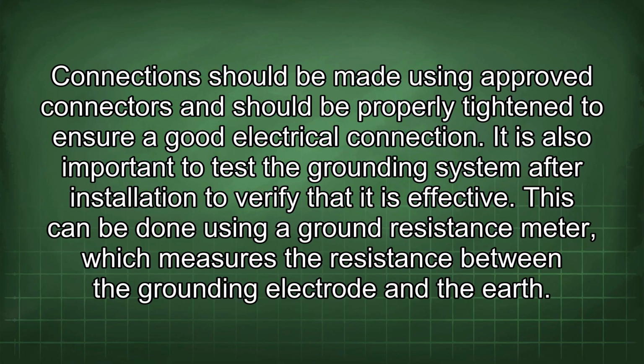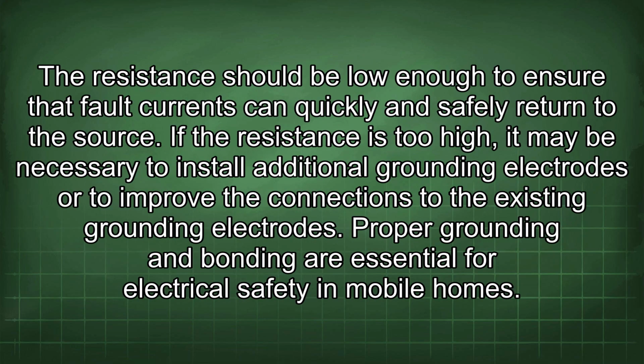This can be done using a ground resistance meter, which measures the resistance between the grounding electrode and the earth. The resistance should be low enough to ensure that fault currents can quickly and safely return to the source. If the resistance is too high, it may be necessary to install additional grounding electrodes or to improve the connections to the existing grounding electrodes.